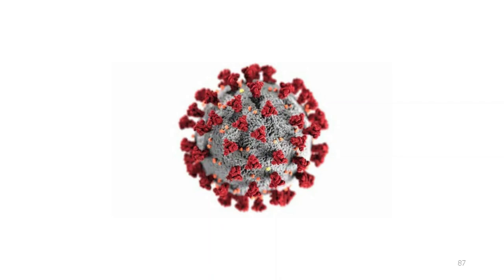Common areas are the biggest concern in multifamily buildings, but unit-to-unit contamination is possible. Single-family homes without visitors pose the least concern. While ASHRAE and others are pushing for more ventilation, Martin Holliday comments in his recent article on Green Building Advisor that other authorities note that super-spreading events aren't being reported in buildings with well-designed and properly functioning ventilation systems, so existing ventilation standards may be just fine.